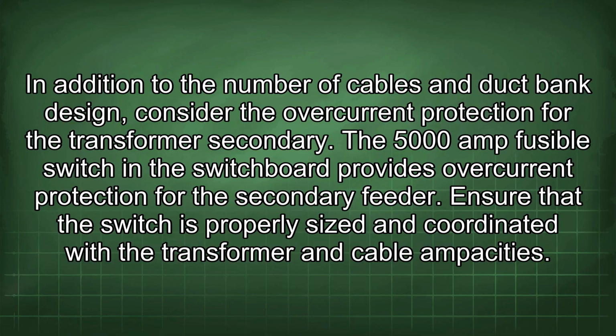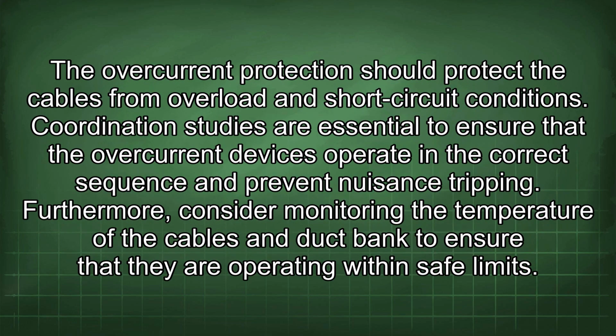The 5000 amp fusible switch in the switchboard provides overcurrent protection for the secondary feeder. Ensure that the switch is properly sized and coordinated with the transformer and cable ampacities. The overcurrent protection should protect the cables from overload and short circuit conditions. Coordination studies are essential to ensure that the overcurrent devices operate in the correct sequence and prevent nuisance tripping.